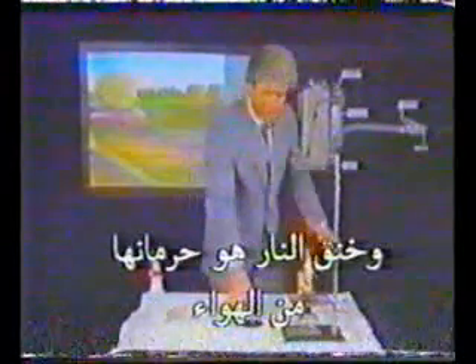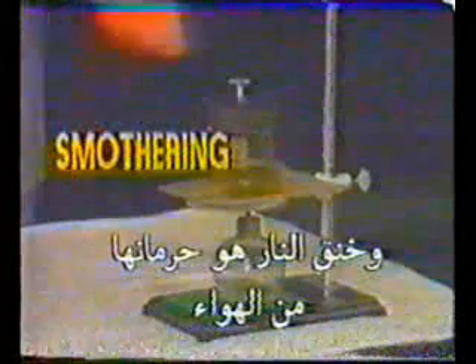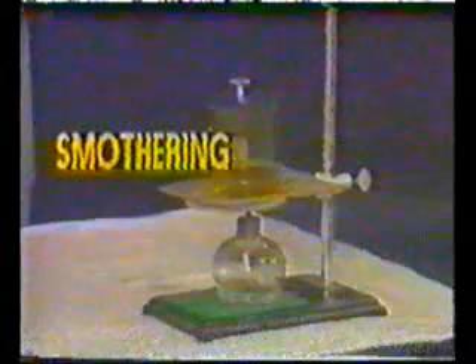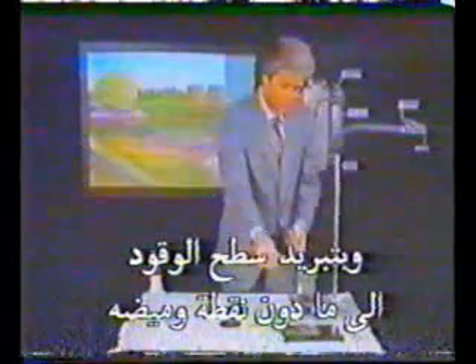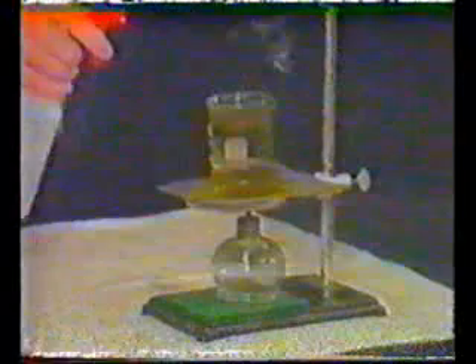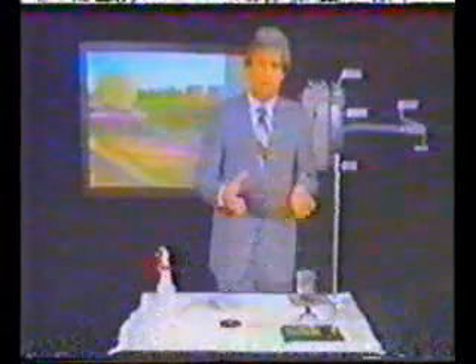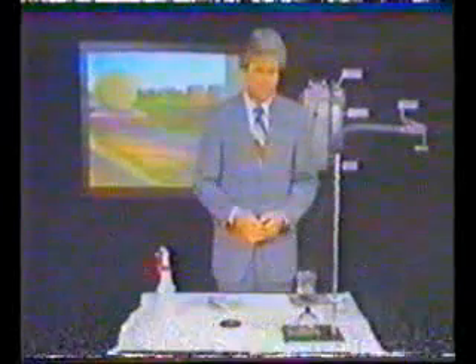Fires can be extinguished by smothering. To smother a fire, you deprive it of the air or oxygen it needs to burn. A fire can also be stopped by cooling the surface of the fuel below its flash point. Cooling the surface of the burning fuel retards the formation of vapors, and when the vapor-air mixture becomes too lean, combustion will stop. This method of extinguishing a fire is called quenching.